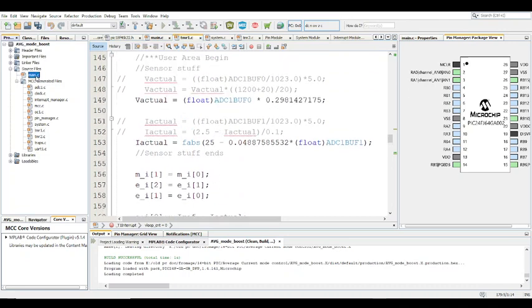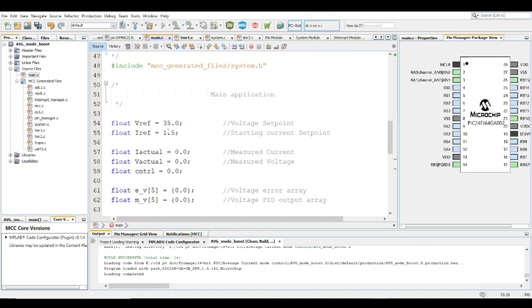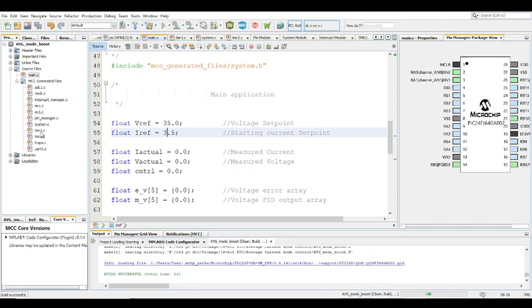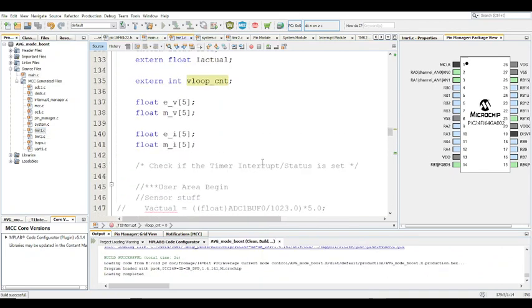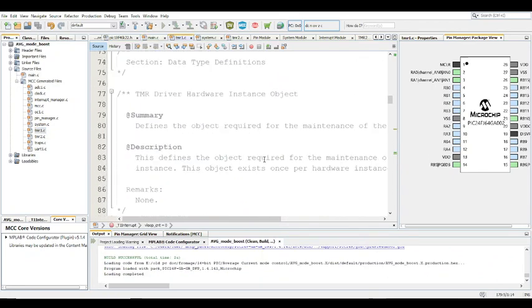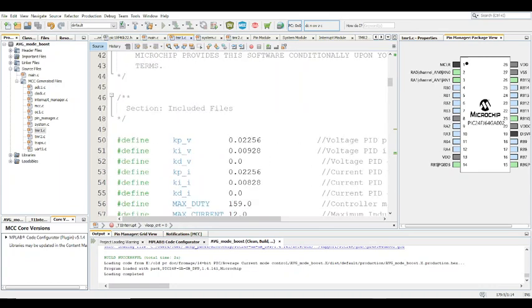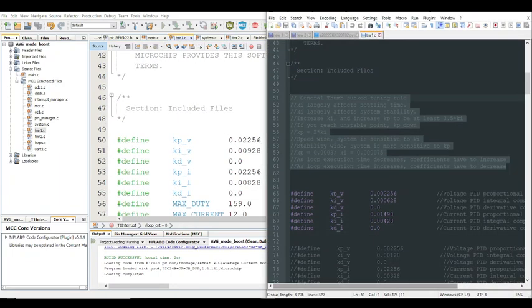So in the main part, I set the Iref to 1.5. Let me change that to 3.5. And so if you go to timer 1, there's a couple of pointers I put up here on how to choose your coefficient. I haven't yet. Let me do that now.